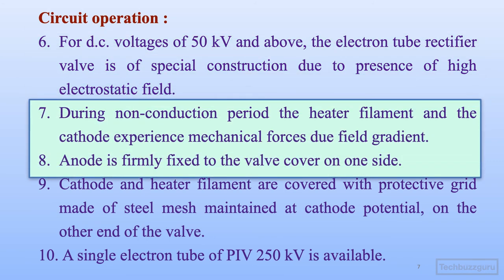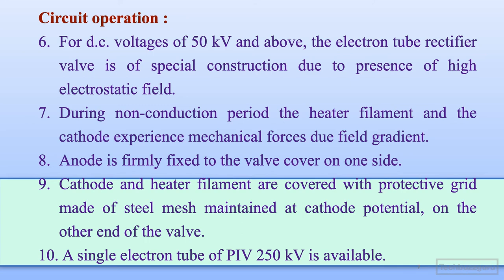During the non-conduction period, the heater filament and cathode experience mechanical forces due to the field gradient. The anode is firmly fixed to the valve cover on one side. The cathode and heater filaments are covered with a protective grid made of steel mesh maintained at cathode potential on the other end of the valve. A single electron tube with a peak inverse voltage of 250 kV is available for use in such applications.